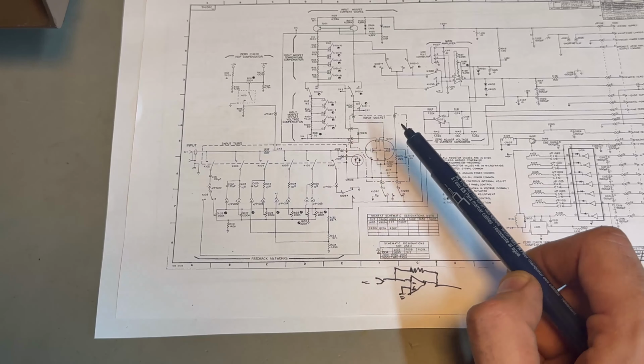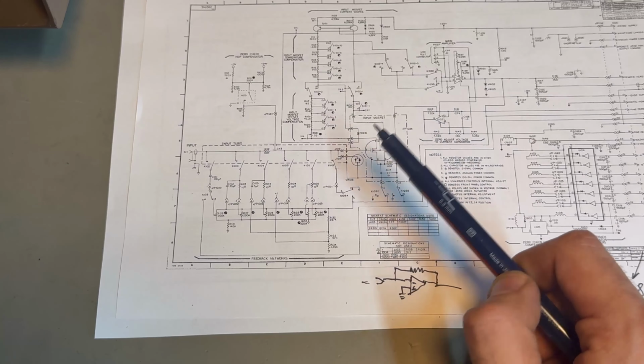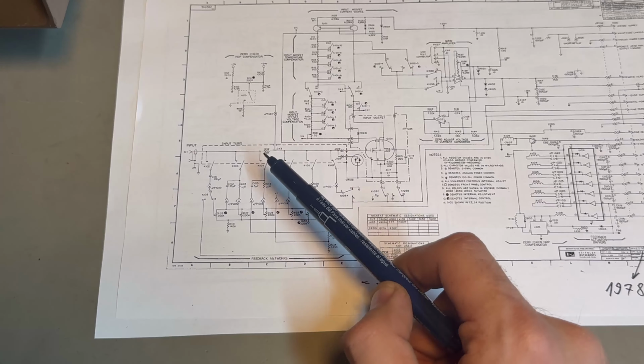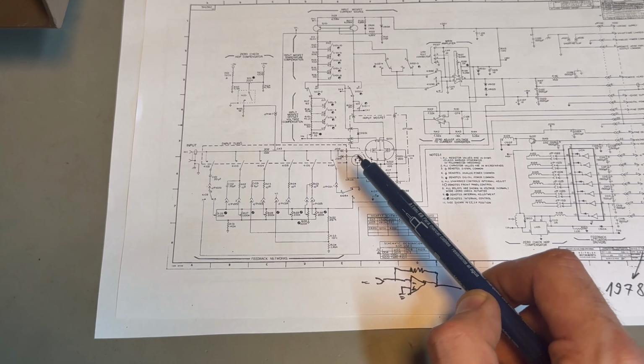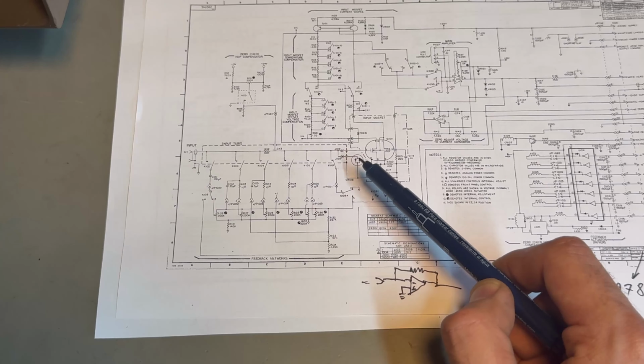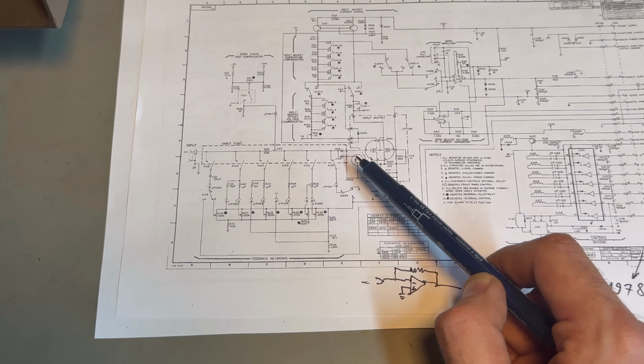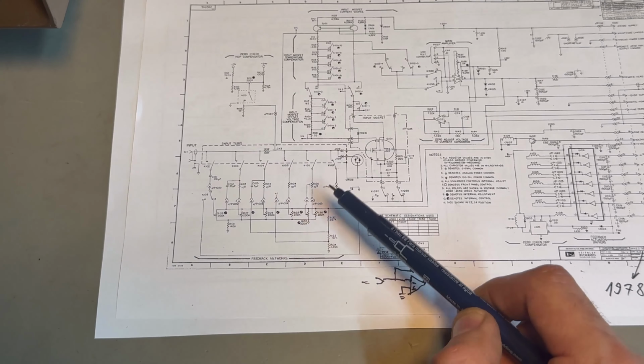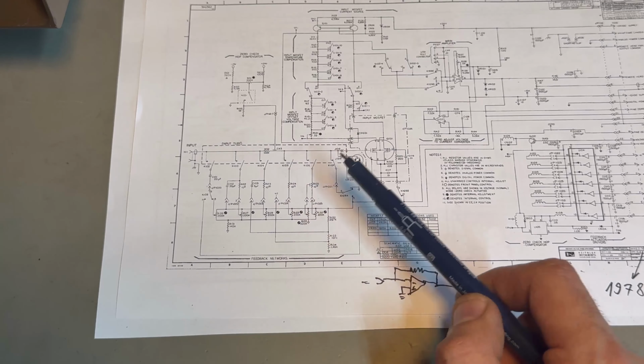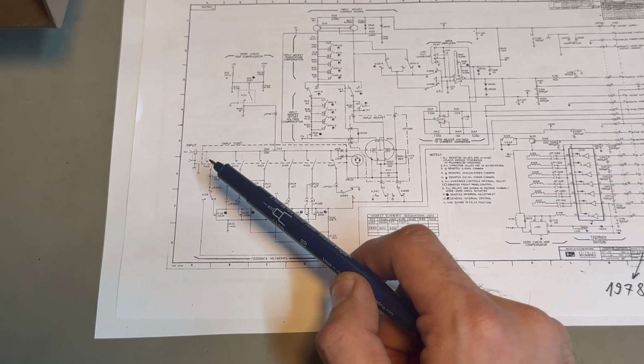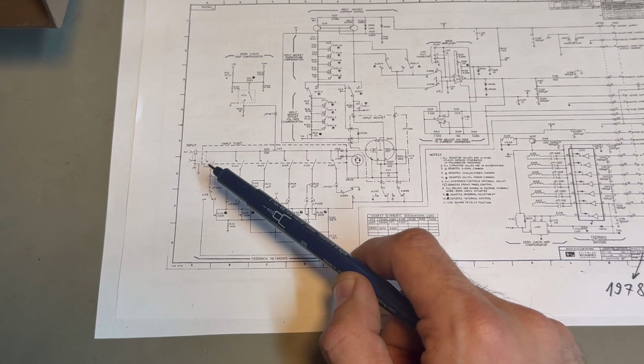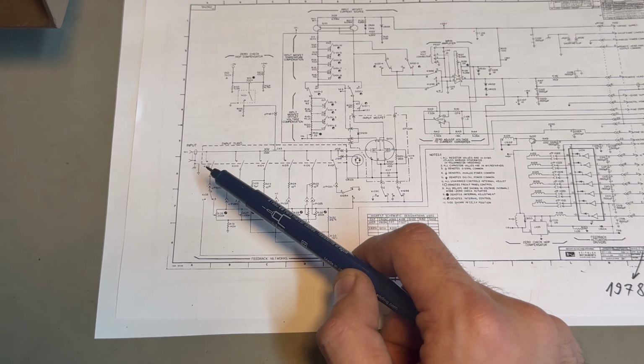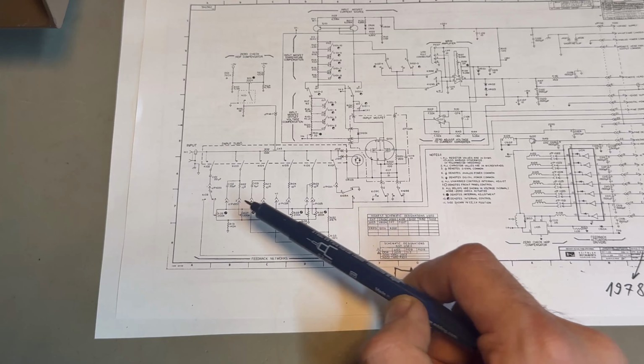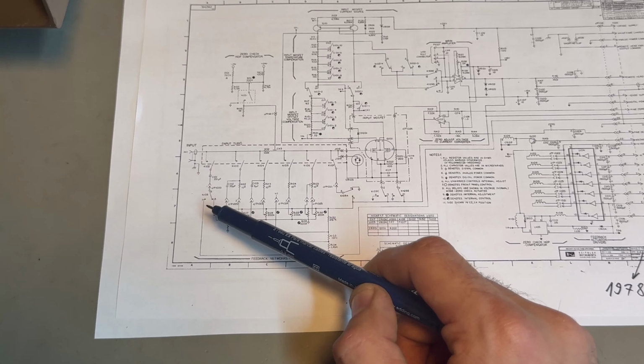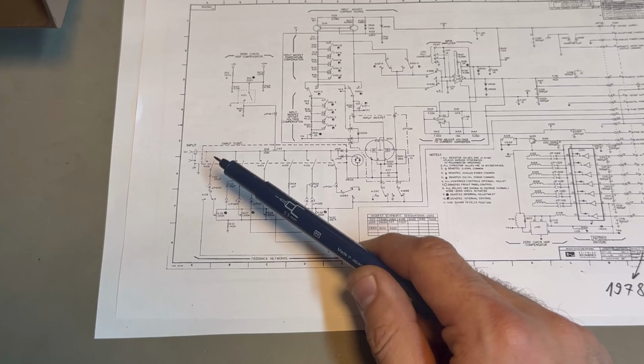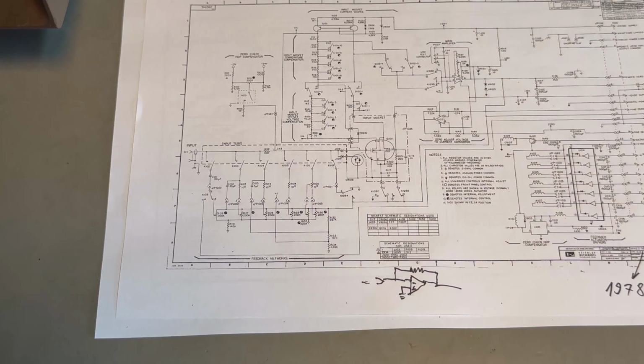Now this electrometer can also act as a very high impedance voltmeter, in which case it only has this 100K resistor in series. It's acting as a gate protection device, and two diodes, and the feedback is basically just non-existent. It turns into a buffer, and it can also act as a basically a charge to voltage converter. So there's a capacitor in the feedback that you can insert, and this will integrate charge over time and give you a voltage.